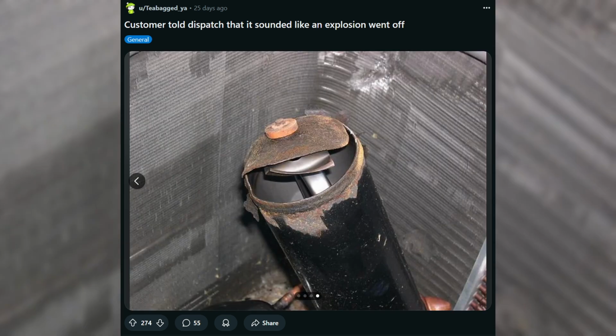That accumulator definitely blew out the bottom. On a heat pump system, whenever it's running in heat pump mode, it doesn't need as much refrigerant flowing through it. That accumulator kind of holds the excess refrigerant that's not needed. Whenever temperatures are lower outside, that shouldn't make it explode by any means, but it definitely did in this case.